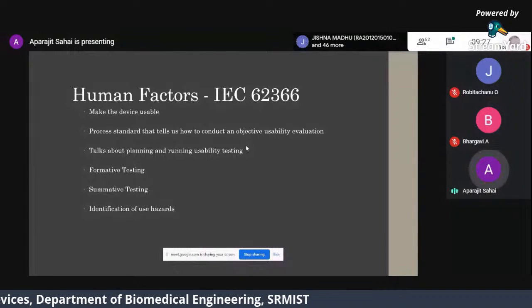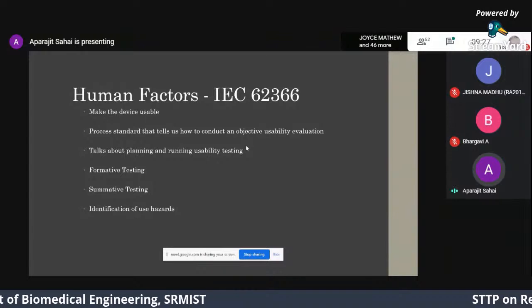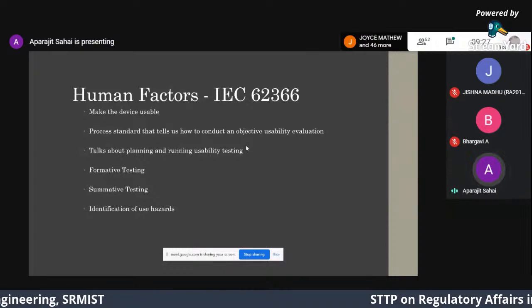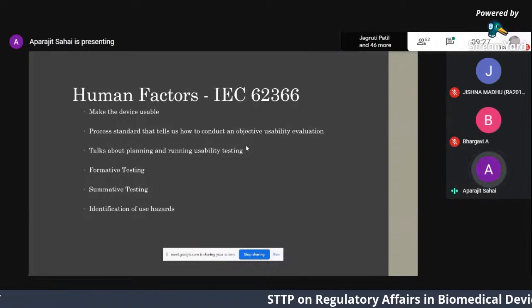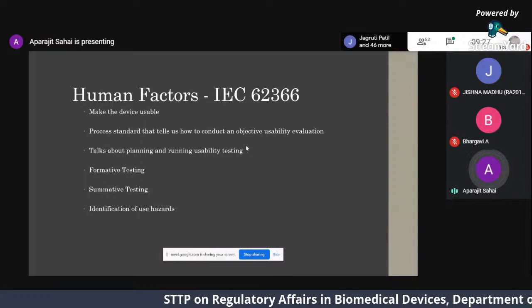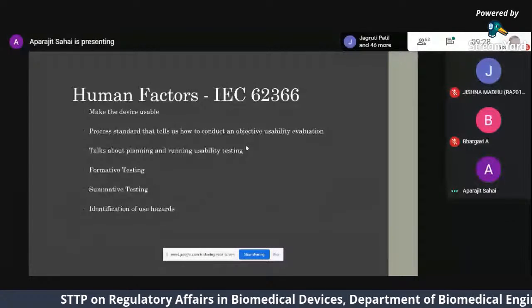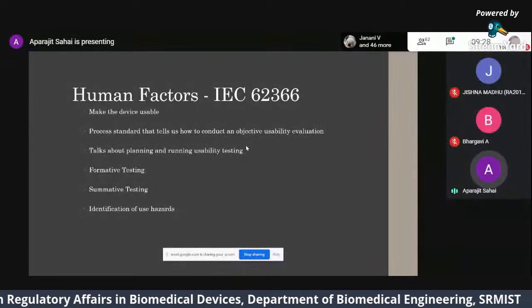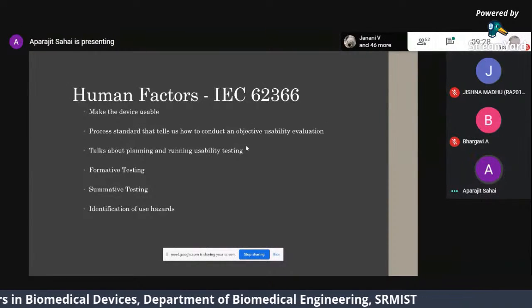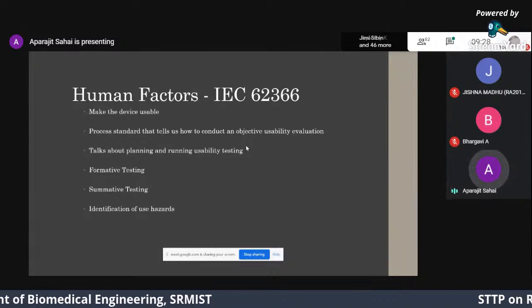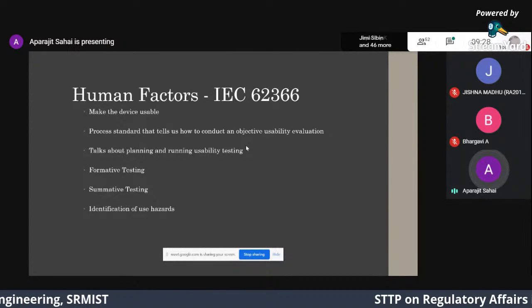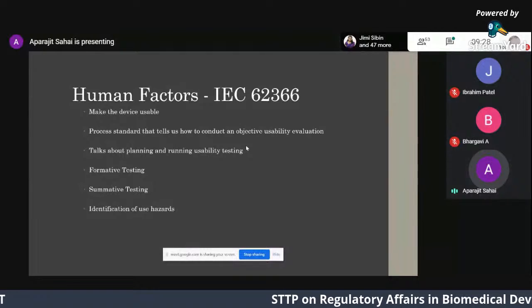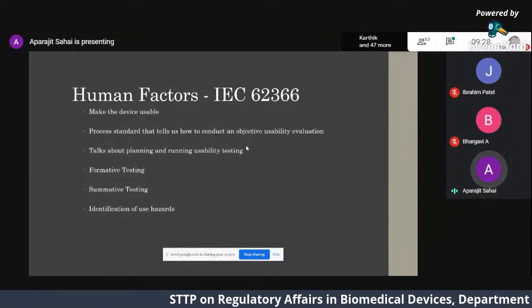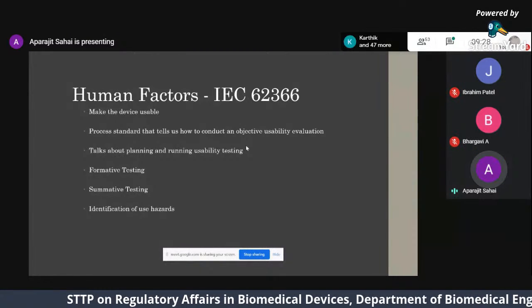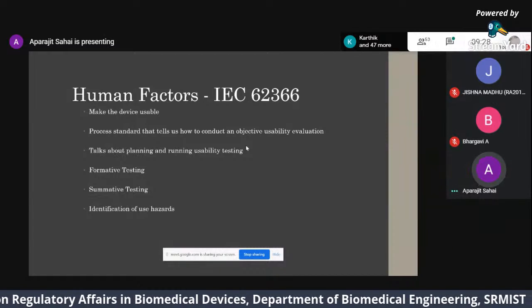Human factors, I know I touched upon this yesterday, but essentially, human factors is a process standard that tells you how to make a device usable. There are no technical requirements in there, but it does give you a uniform approach to making a device usable, how to test, how to do usability testing. That's essentially what this focuses on. It talks about how you plan usability testing and how you run a usability test. It talks about two specific kinds of testing, formative and summative.